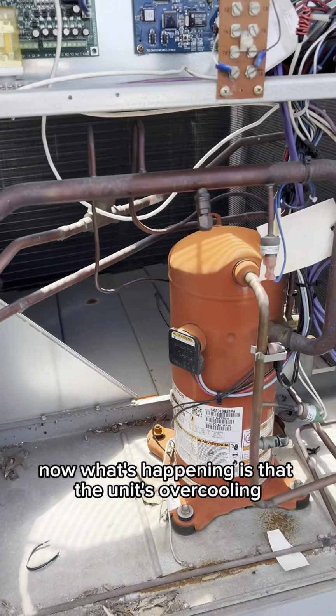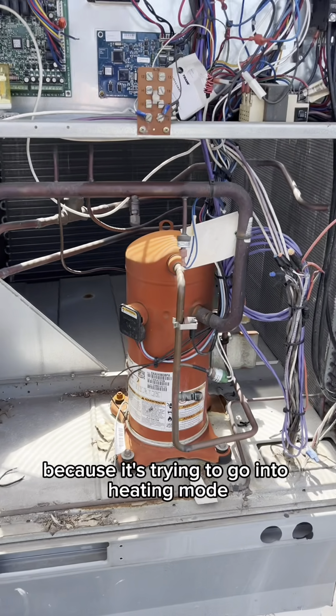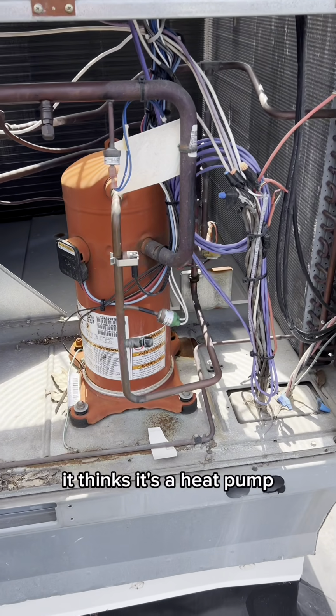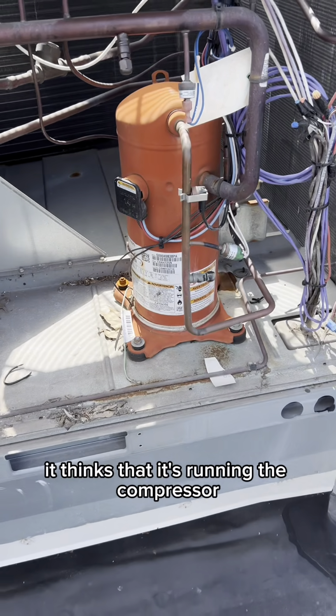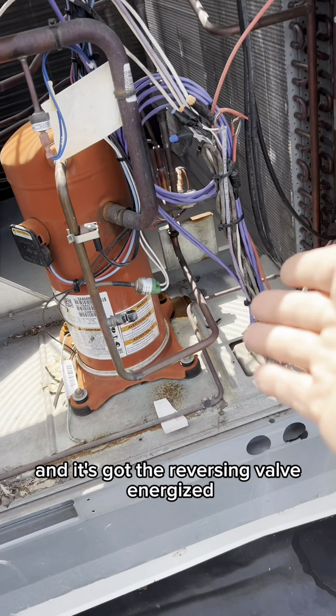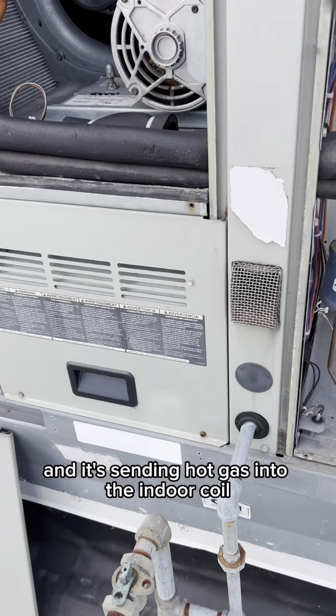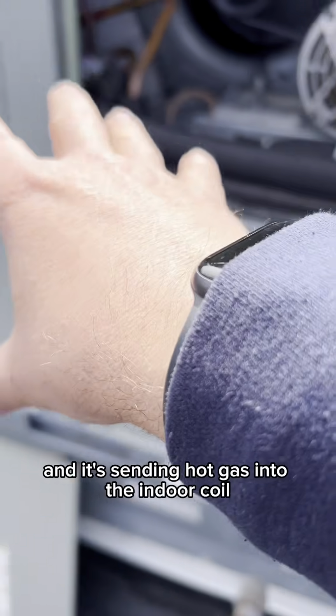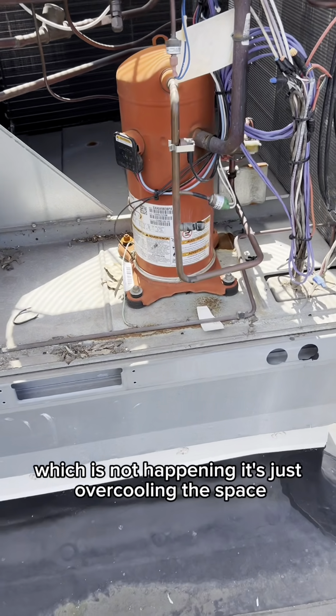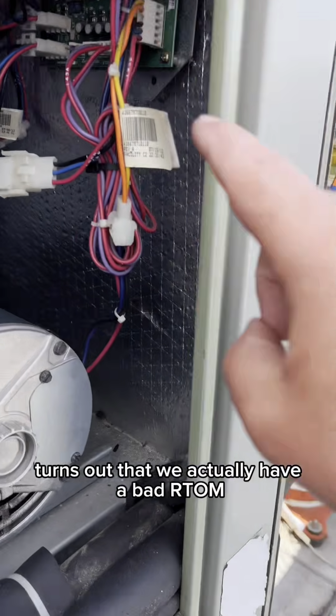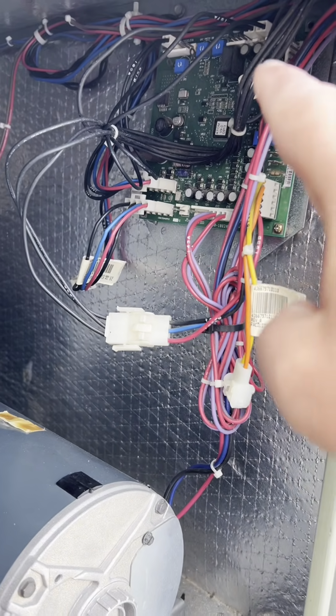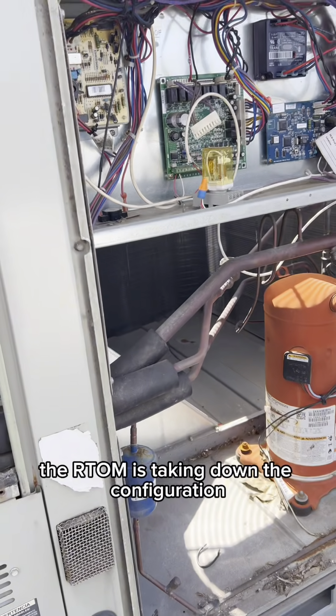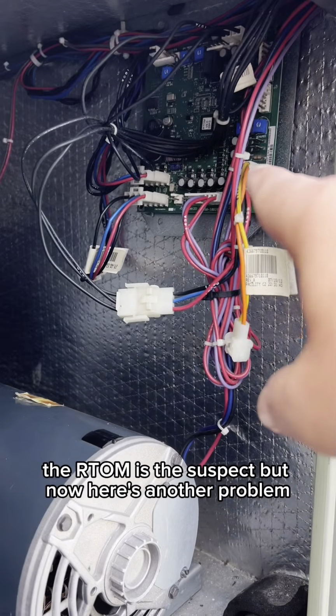Now, what's happening is that the unit's overcooling because it's trying to go into heating mode. It thinks it's a heat pump, so guess what? It's running the compressor. It thinks that it's running the compressor, and it's got the reversing valve energized, and it's sending hot gas into the indoor coil, which is not happening. It's just overcooling the space. Turns out that we actually have a bad RTOM. The RTOM is taking down the configuration. The RTOM is the suspect.